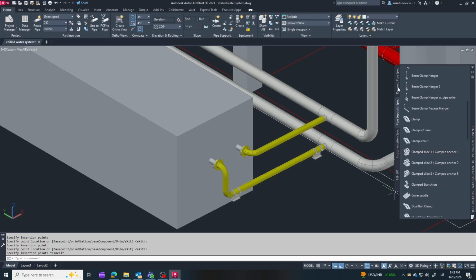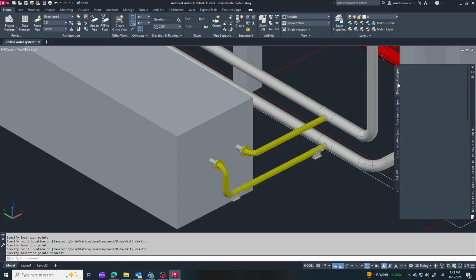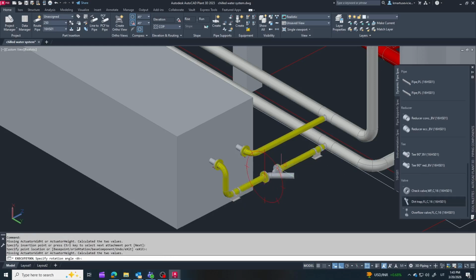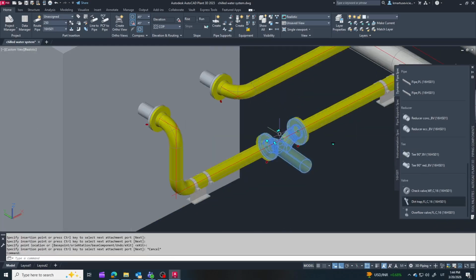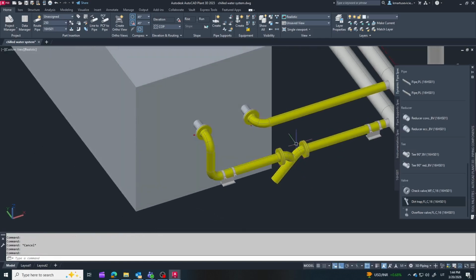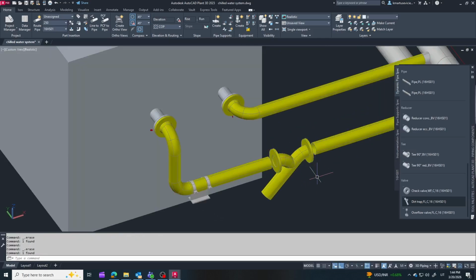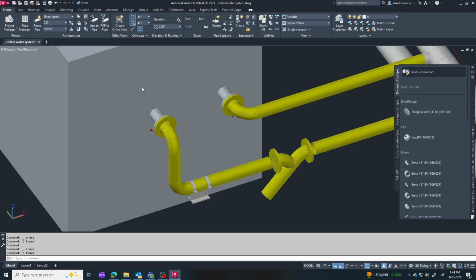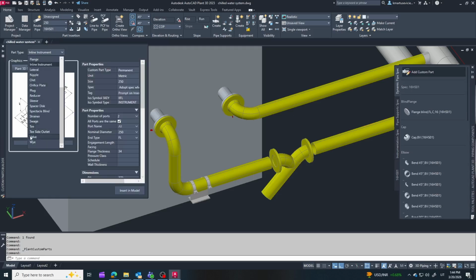On the inlet line, the first component is a strainer. It protects the internal components of the chiller from dirt and particles. Next, we add isolating valves. This allows us to shut off the flow and service the strainer when needed. Butterfly valves are very commonly used as isolating valves in water systems.